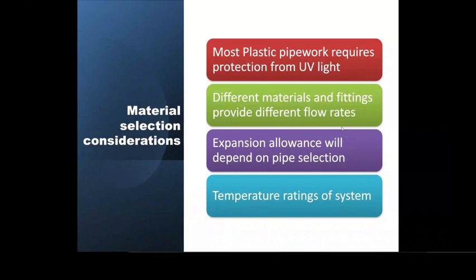Everything originally was set up for low pressure. If you're not upgrading the hot water cylinder, and you suddenly expect the old system to work with all these extra friction losses, you can have some negative outcomes, and basically you can get a system that doesn't deliver what the customer's expecting. And once it's all finished, it's very hard to go back and rectify that. So definitely you need to try and minimize the amount of fittings, or make sure that you've got adequate pressure to compensate for the flow loss you're going to experience.